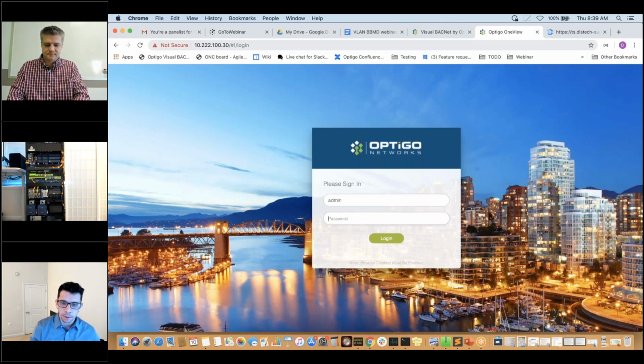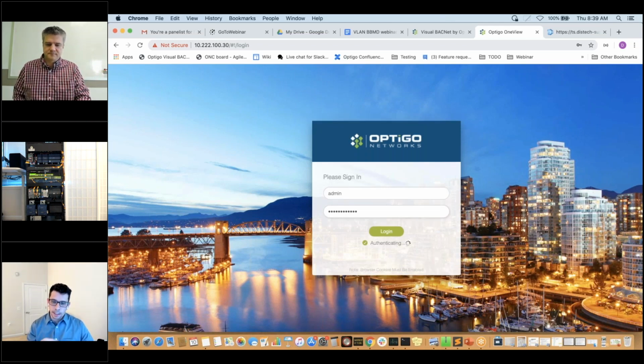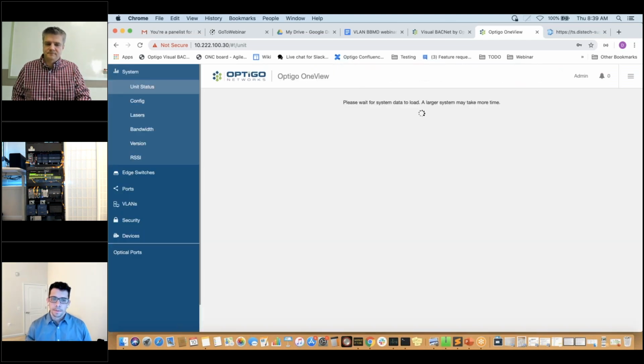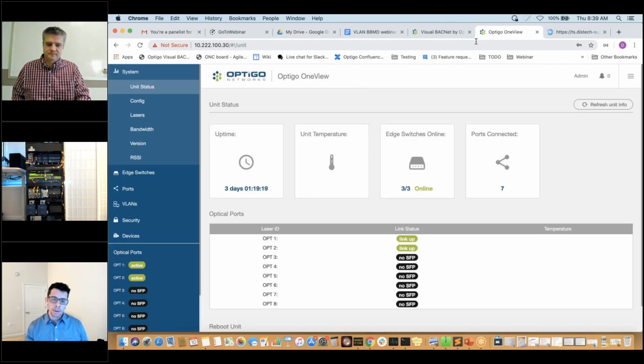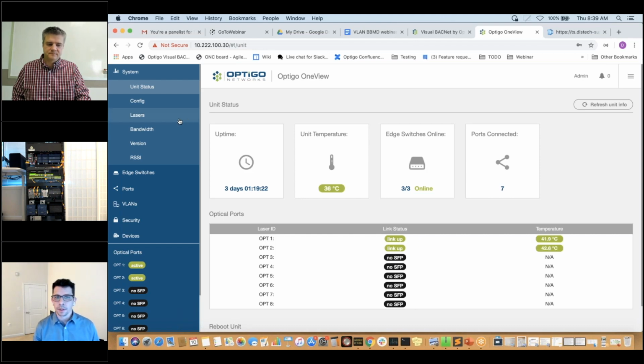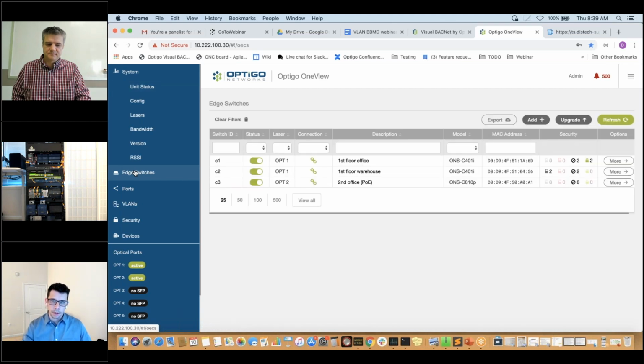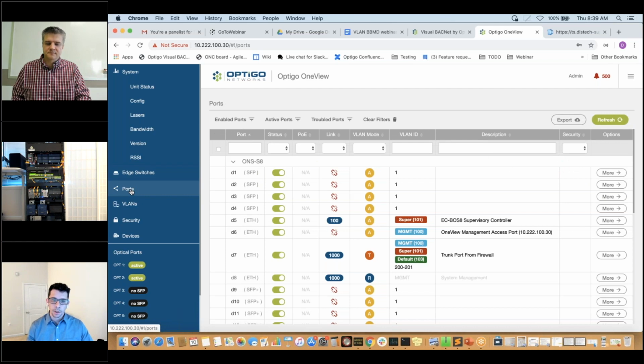So just to add a little bit to what Dave was talking about prior, we're all mostly accustomed to MSTP devices and setting up an MSTP trunk. And that basically, on older jobs or in the past, took care of your network segregation for you. You would have one MSTP trunk, and it was isolated from another MSTP trunk. And typically, you would bring those into some supervisory controller, and you might not even do peer-to-peer linking across them.